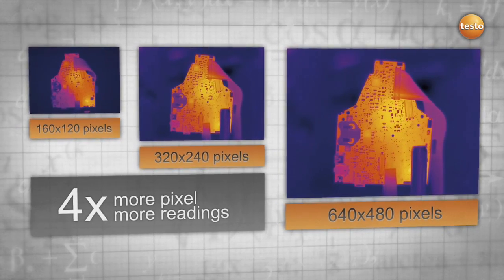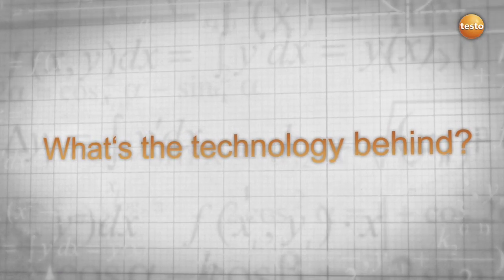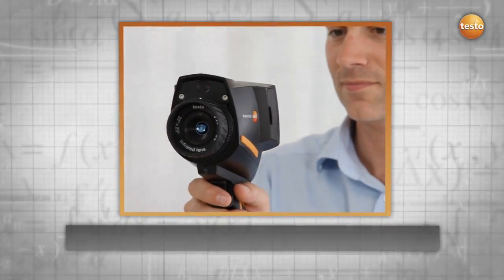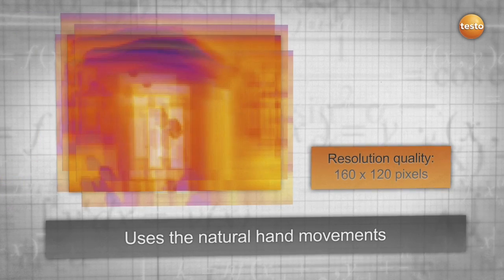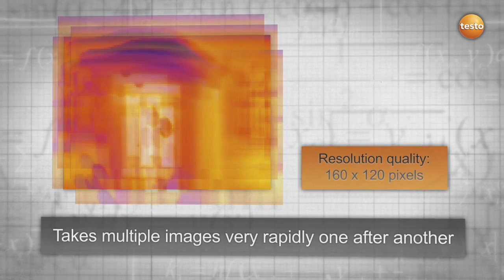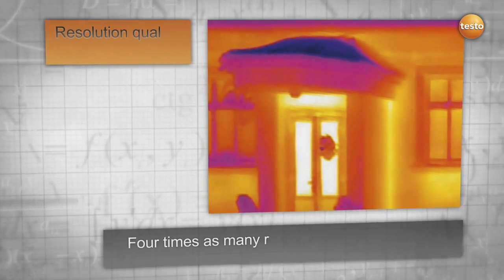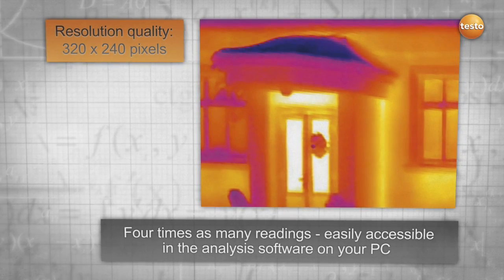The Super Resolution technology uses natural hand movement and takes multiple images rapidly, one after another, which are slightly shifted to each other. Using an algorithm, these images are then calculated to obtain one image. The result: four times as many readings and a much better thermal image resolution.